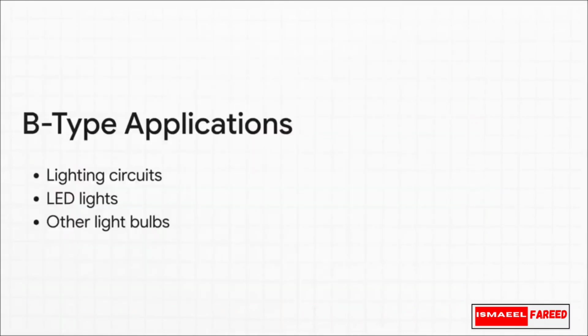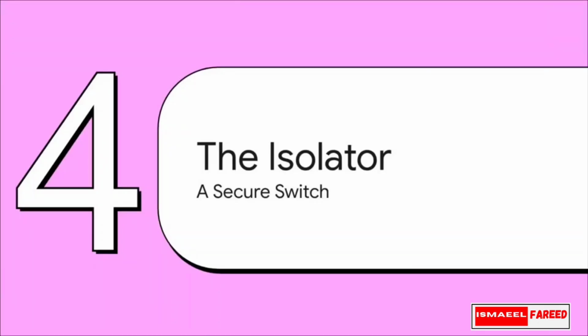The perfect real-world examples for B-types are dedicated lighting circuits, especially modern LED lights and similar low-draw bulbs. LEDs are so incredibly energy efficient, right? They simply don't need a massive jolt to illuminate. And because their starting current is just so incredibly low, a highly sensitive B-type breaker is the absolute perfect match to protect them. And finally, Section 4, the isolator exception.